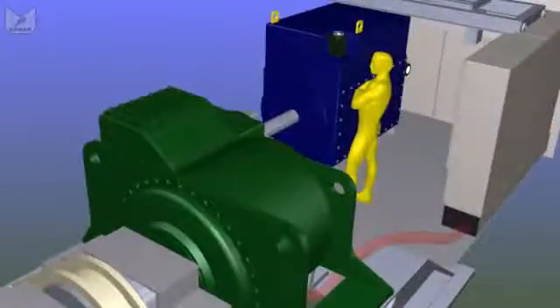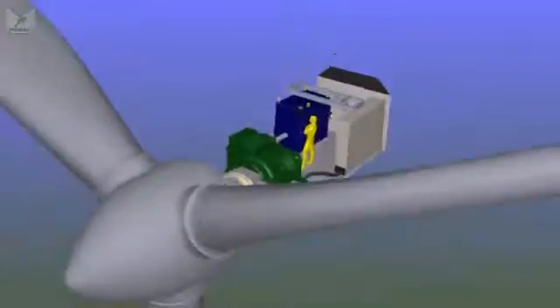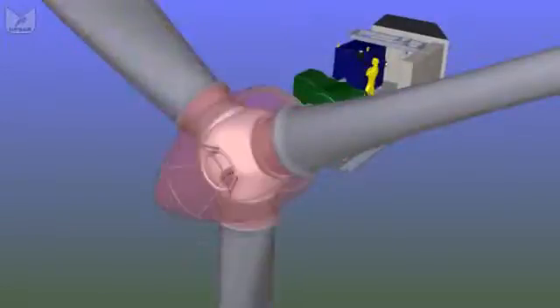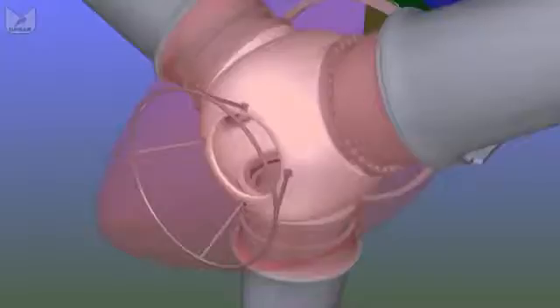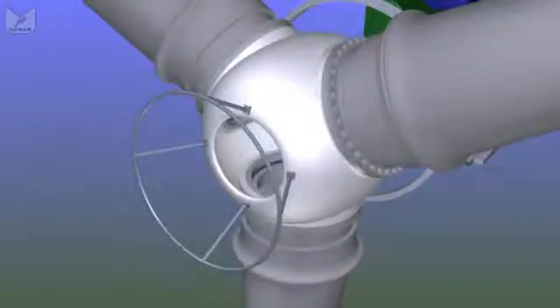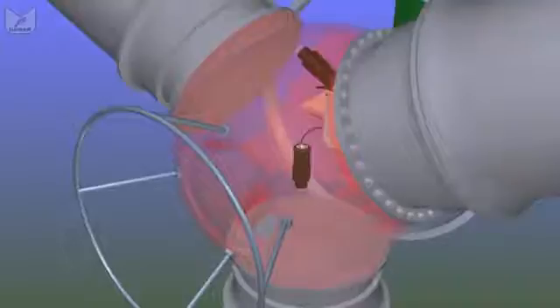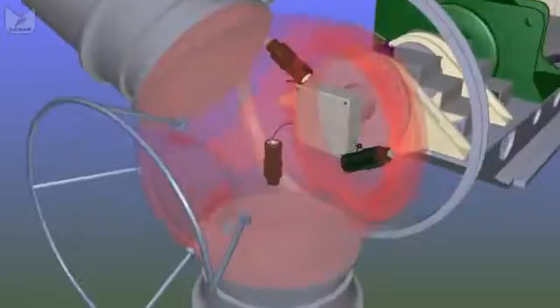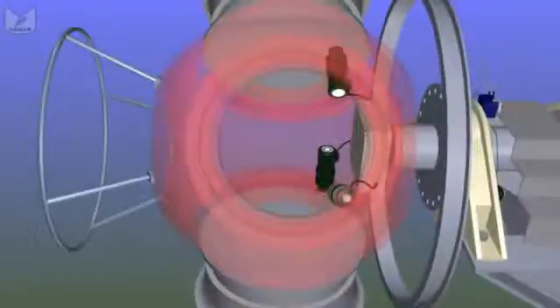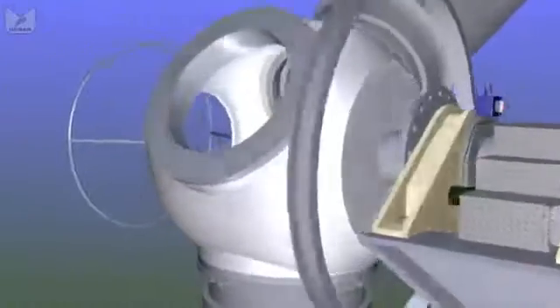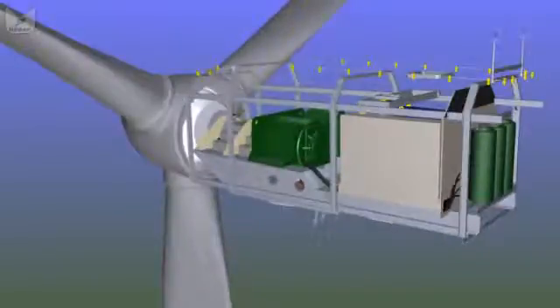That as an overview is pretty much all there is to it. The only thing left to talk about are the blades, which actually do the work. We still have three of them, they still pitch - in other words they twist on themselves to line up with the wind. You access the hub through the gap between the fiberglass cowl and the cast hub. You wriggle through usually feet first, crawl through the hole in the middle of the hub. Inside the hub we'll find the control electronics, the pumps, the motors, and the batteries to control the pitch of each blade, rotating it on its own bearing to set the optimum angle for the wind. If we turn the blades through 90 degrees so they're edge onto the wind, there's no net turning force. It's a process called feathering and the turbine will stop.